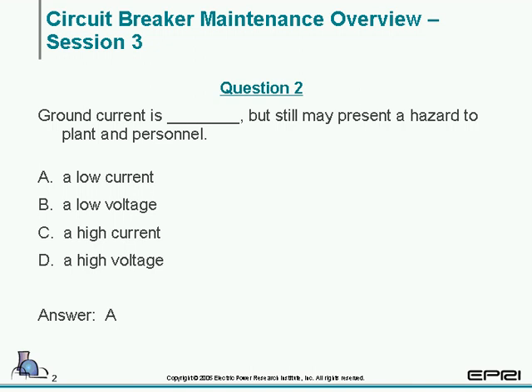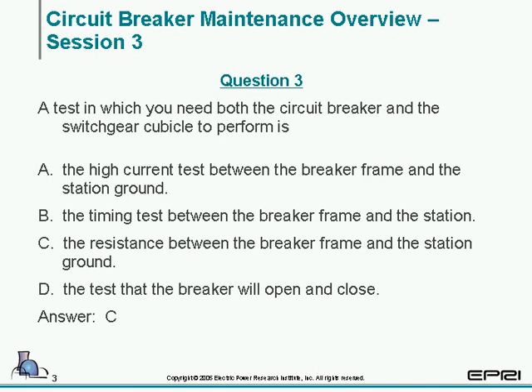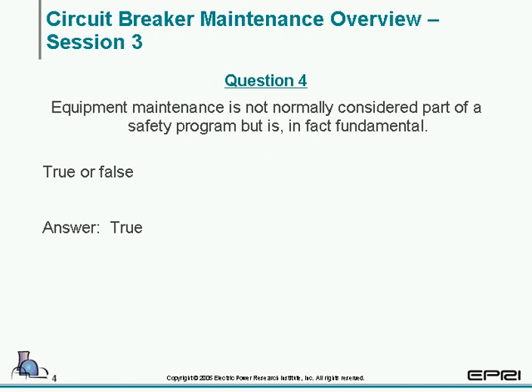Question 2, ground current is blank, but still may present a hazard to plant and personnel. Answer is A, a low current. Question 3, a test in which you need both the circuit breaker and the switchgear cubicle to perform is C, resistance between the breaker frame and the station ground. Question 4, equipment maintenance is not normally considered part of a safety program, but is, in fact, fundamental. That is true.